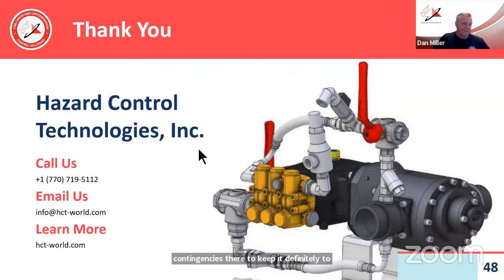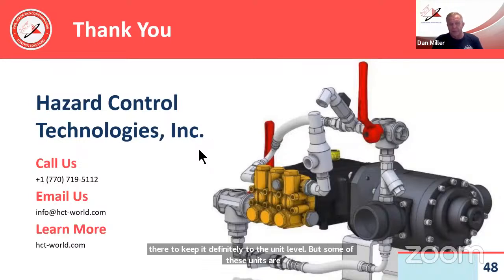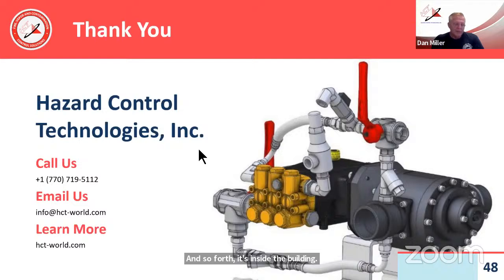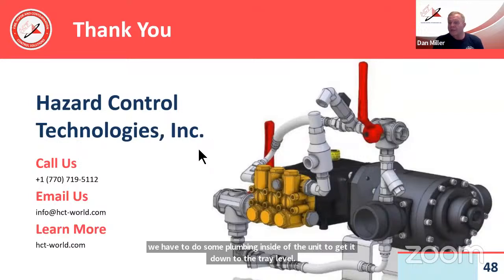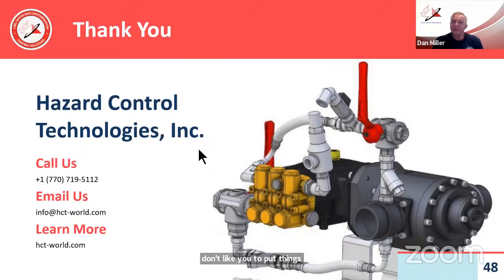But some of these units are inside of buildings. If you think of a data center and where the UPSs are located and so forth, it's inside the building. So some design considerations need to be taken into account there. Some UPS units that are going in data centers have an open ventilated top, so it's fairly easy to get F500 into the BESS unit, but we have to do some plumbing inside of the unit to get it down to the tray level. And some manufacturers don't like you to put things inside of their BESS unit or their enclosure. So there's some things that have to be worked with there from our engineering support team, as well as the manufacturer of the BESS unit. But we have designed for some BESS companies and they have accepted our design.